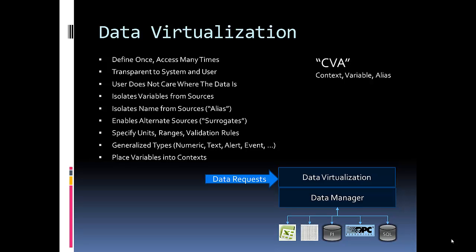If the value, while the process is operating, needs to be between 1,000 and 5,000, then something abnormal is happening. So we have something called an operating range and a base range for validity checking, and you can have all sorts of ranges applied in there.